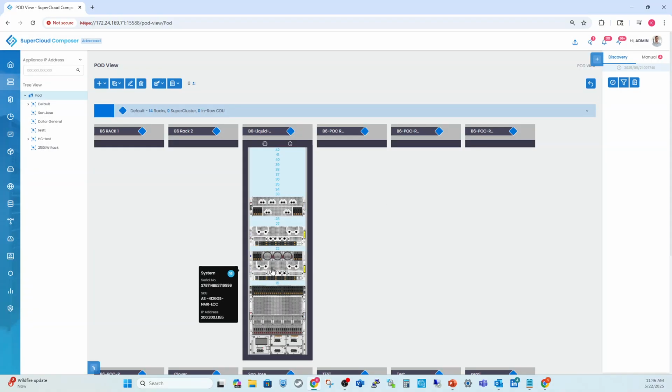So we can also look here. This is the MI325 platform, which is basically an AMD Instinct platform. You can see here the serial number gets exposed, the BMC IP address, and then also the rack slot unit position, the starting position. You can see in the front here the various hoses coming out of the front of it that are connected into the manifold of the rack itself, providing liquid cooling for this rack. You can see here on the top that it's represented by a PDU.